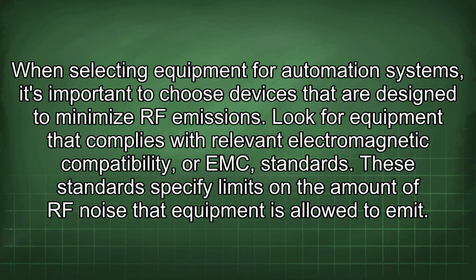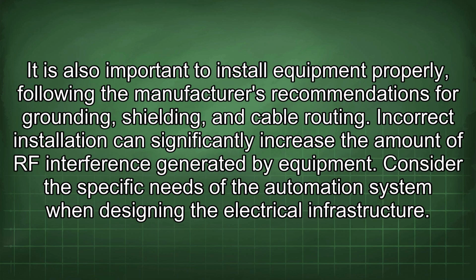When selecting equipment for automation systems, it's important to choose devices that are designed to minimize RF emissions. Look for equipment that complies with relevant electromagnetic compatibility, or EMC, standards. These standards specify limits on the amount of RF noise that equipment is allowed to emit. It is also important to install equipment properly, following the manufacturer's recommendations for grounding, shielding, and cable routing. Incorrect installation can significantly increase the amount of RF interference generated by equipment.